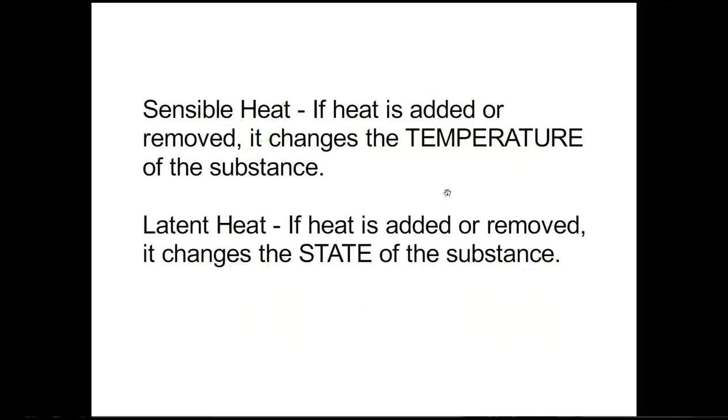All right, in air conditioning, we have two types of heat that we like to talk about. One is sensible heat, and that is where if you add heat energy, or molecules in motion, to a substance, it changes the temperature that you can measure with a thermometer. And then we have latent heat, and latent means hidden. And that's heat that cannot be measured by a thermometer.